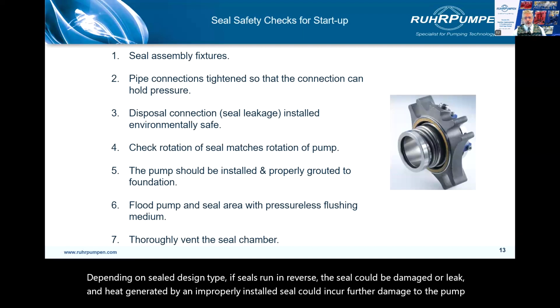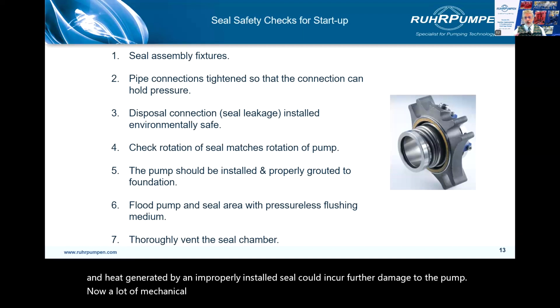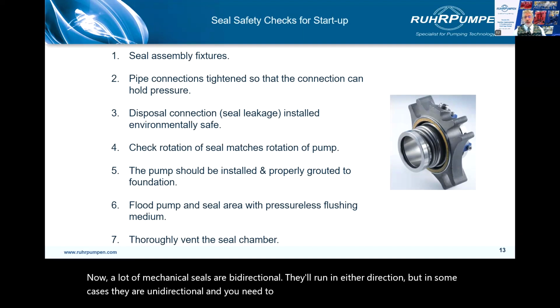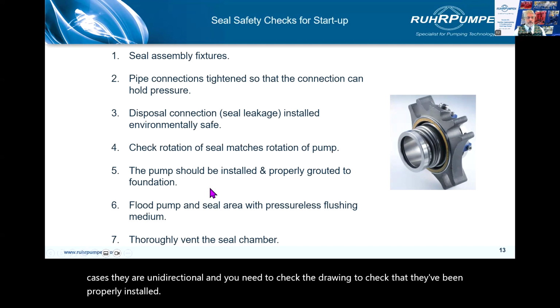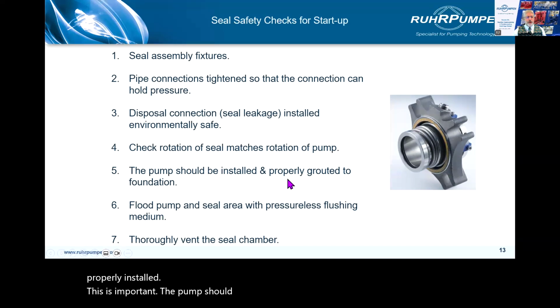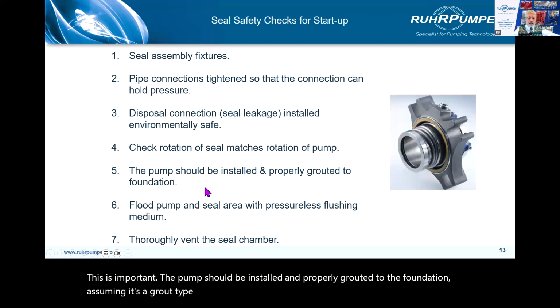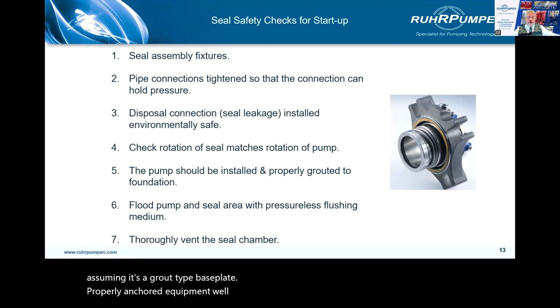Now, a lot of mechanical seals are bidirectional. They'll run in either direction, but in some cases they are unidirectional, and you need to check the drawing to check that they've been properly installed. This is important. The pump should be installed and properly grouted to the foundation, assuming it's a grout type base plate. Properly anchored equipment will eliminate potential vibration, which could cause premature seal failure.